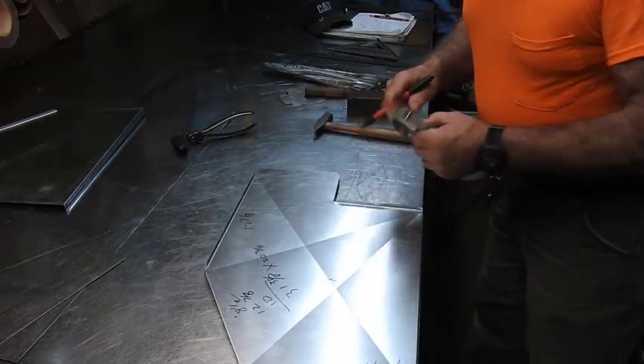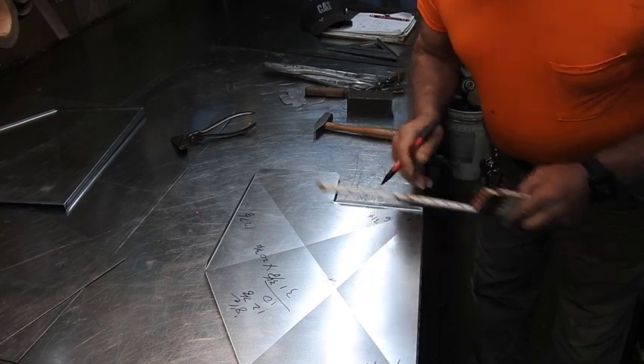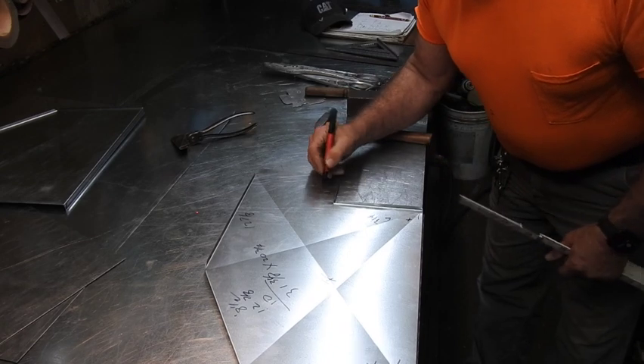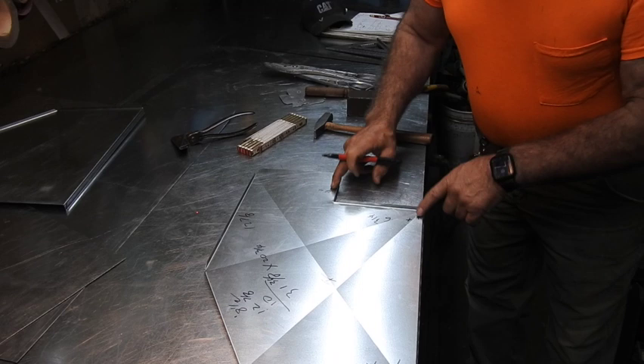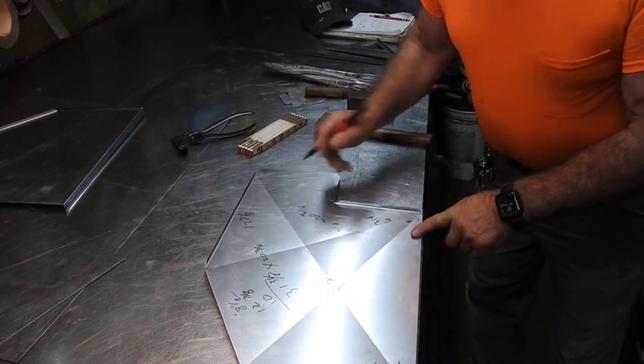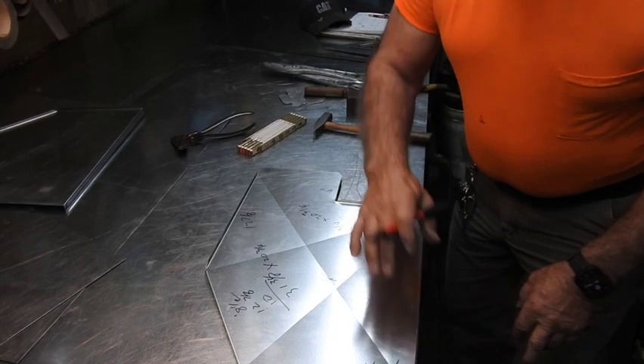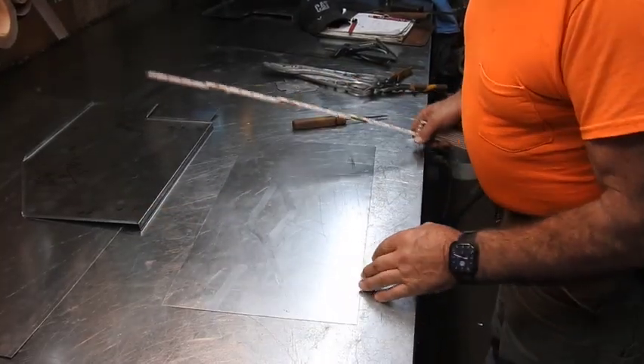Inside here we're going to have 6 and 3 quarter plus 5 down here. This should be a 4 inch throat — I'd like to make a standard 4 inch throat if at all possible. So that's 6 and 5 is 11 and 3 quarter. So 11 and 3 quarter by 20 and 3 quarter — that's going to be the dimension of the cut size for the toe wrapper and the heel wrapper. This piece of scrap here is going to be just about perfect for that.